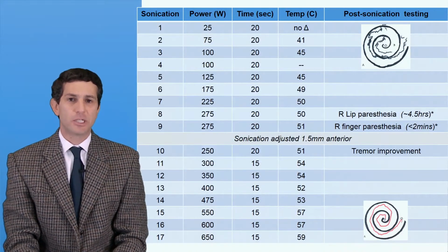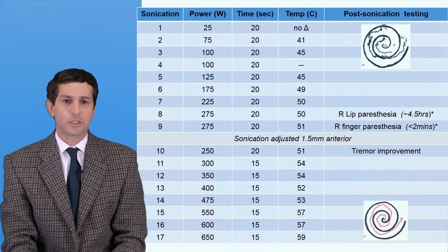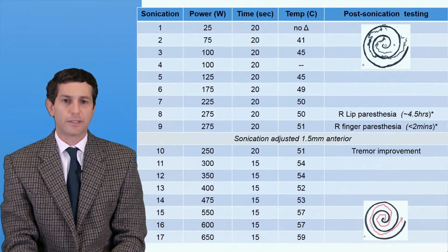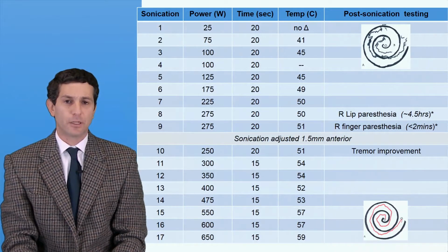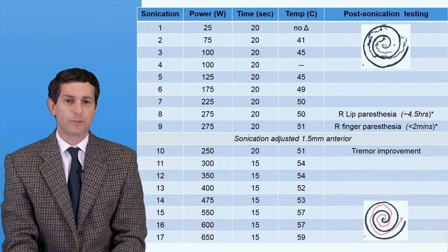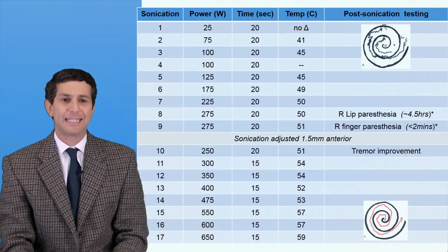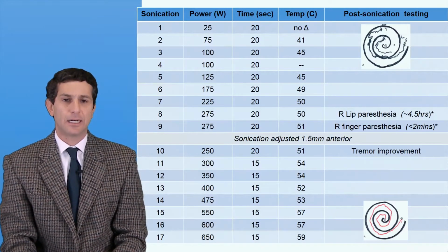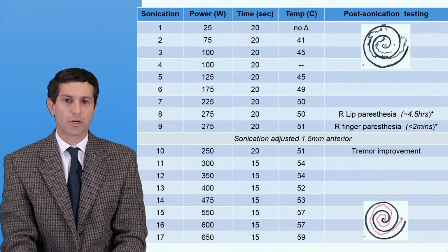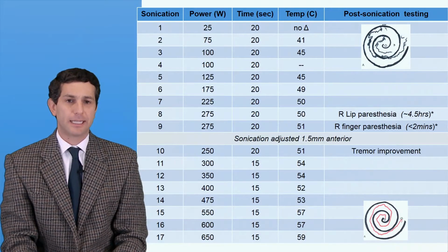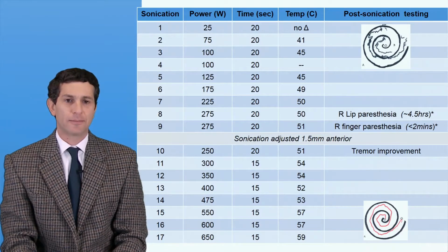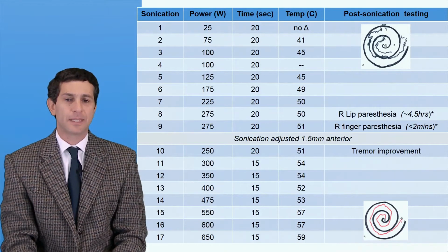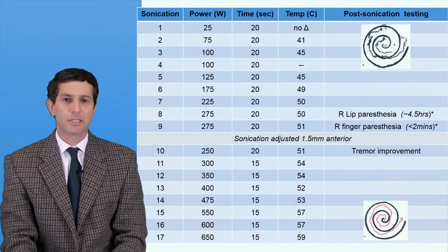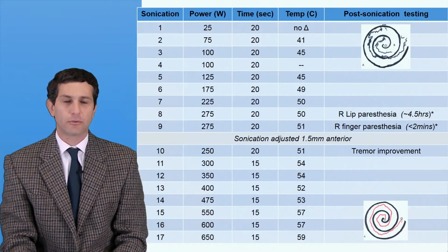And this was the first patient that we treated. And just to walk you through the prescription of his treatment, the first sonication was at very low power, 25 watts for a duration of 20 seconds, and it did not cause any heating at the stereotactic target. And then we gradually escalated the acoustic power until we could start to see a thermal rise at the target. And you can see at sonications 8 and 9, the patient started to develop some clinical response.